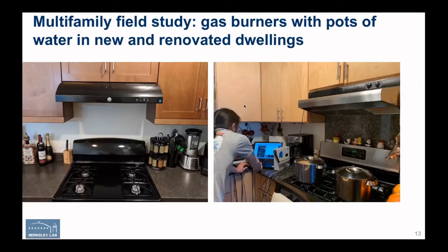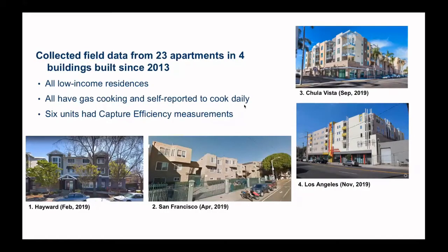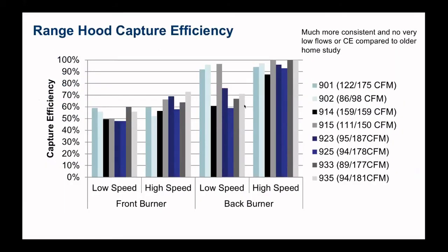The next data is from a more recent study looking at some apartments — gas burners with pots of water in new and renovated dwellings. Importantly, these are brand new installations that haven't had time to plug up with grease or become broken. These are all low income units. In six of the units we measured capture efficiency using the same technique. The different shadings represent the six different apartments. We tested on low speed and high speed, front burner and back burner. Again, you can see a capture efficiency range from a low of about 50% to about 100%. Operating at high speed is obviously better, but it's noisy. We see the same trend — much better capturing on back burners than front burners.